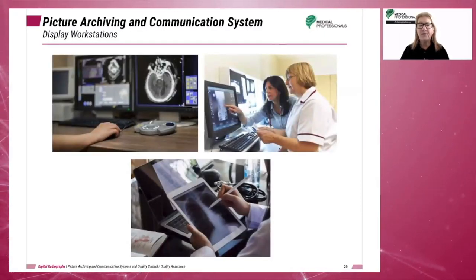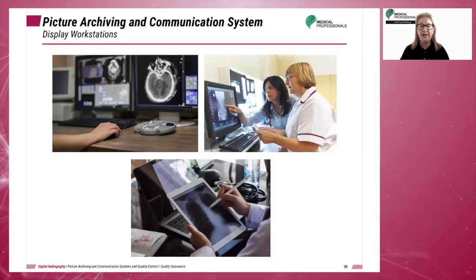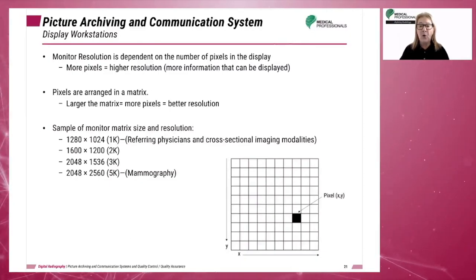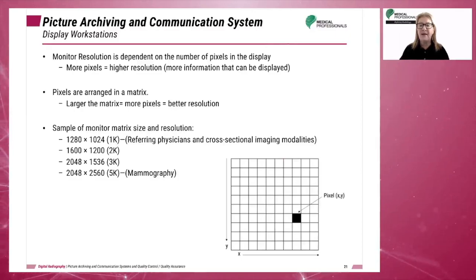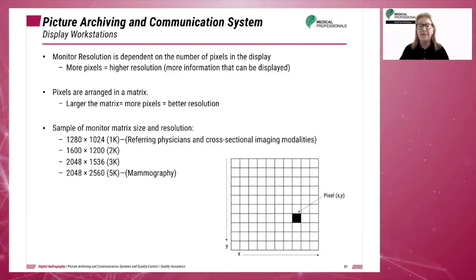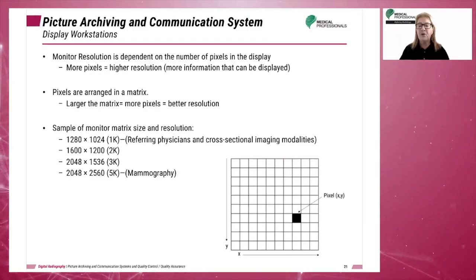Here we see a sample of LCD monitors, which predominate in medical imaging due to their size, price, and quality. Workstation monitors for medical imaging must be of higher quality than monitors used for other applications. Monitor resolution is dependent on the number of pixels in the display — the greater the number of pixels, the higher the resolution. Pixels are arranged in a matrix; a larger matrix size means more pixels, which equals better resolution. Radiologists require the highest resolution monitors for the particular modality.